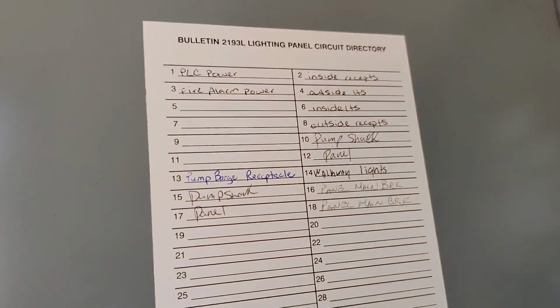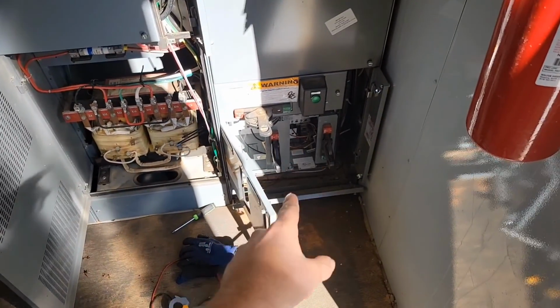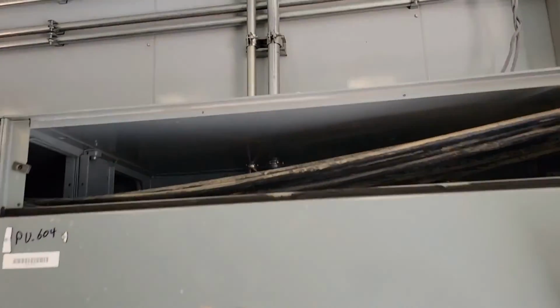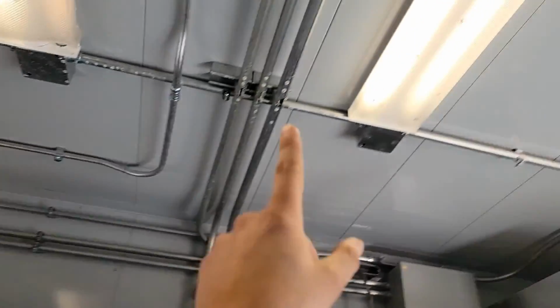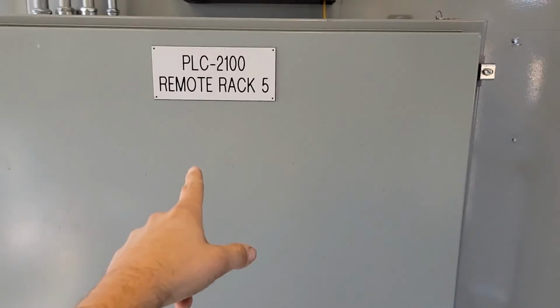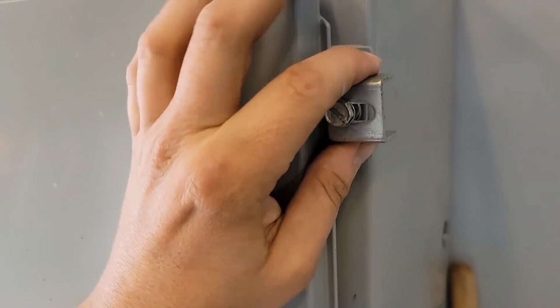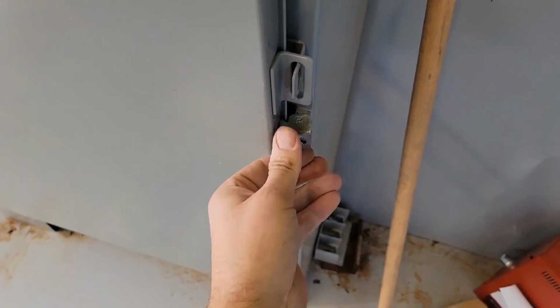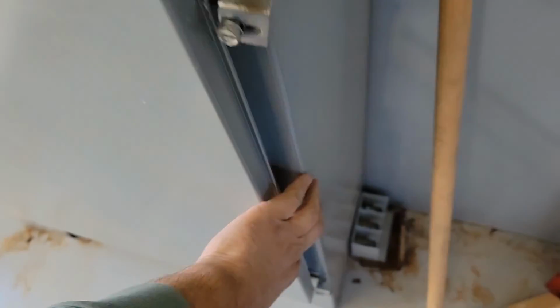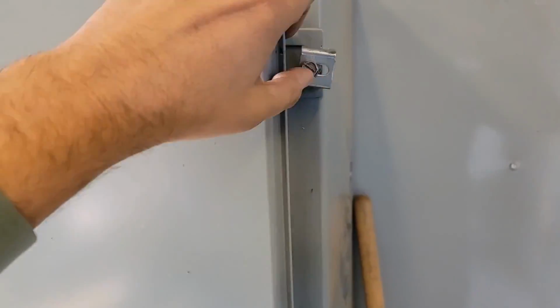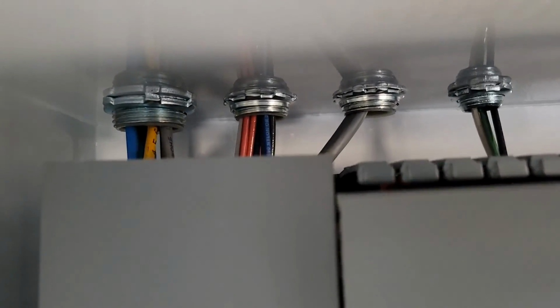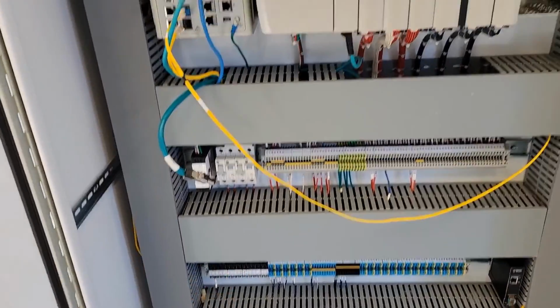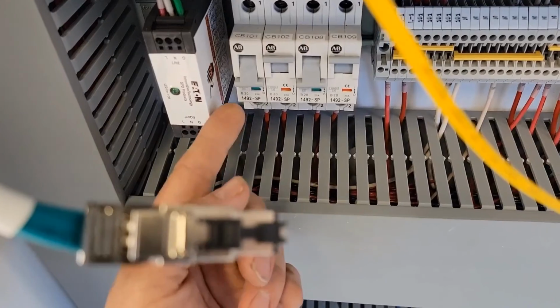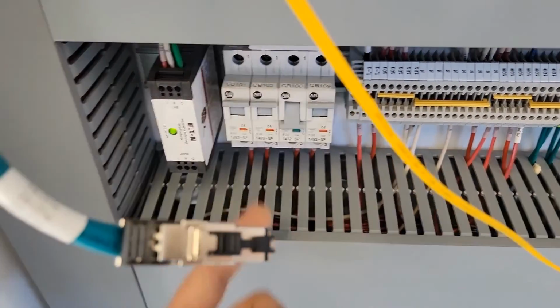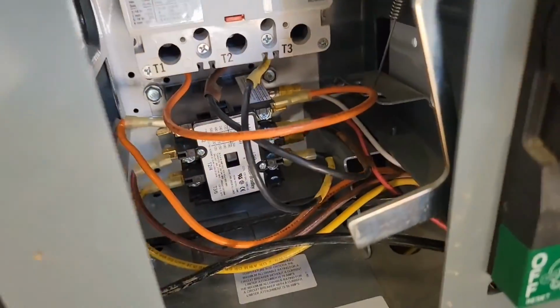Well, nothing happened. Guess I got to keep taking panels off. All right, so we're going from that panel up, over, and then you can barely see it. It goes up into that conduit that's in the middle. It comes down and it goes into this PLC. So you got these flathead screws that I've already loosened up. Okay, there it is, the white and red wire. Now, the problem is in here, and I gotta find it. I have traced the wire down to this breaker right here, 20 amp breaker. Contactor's pulled in now.